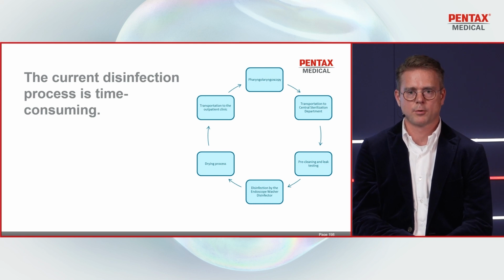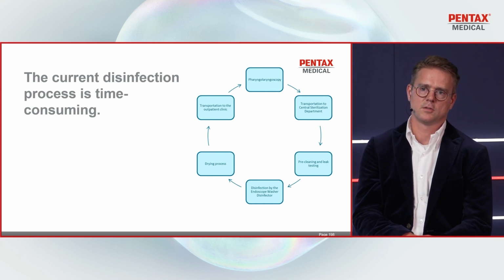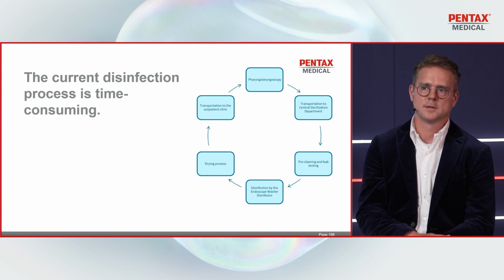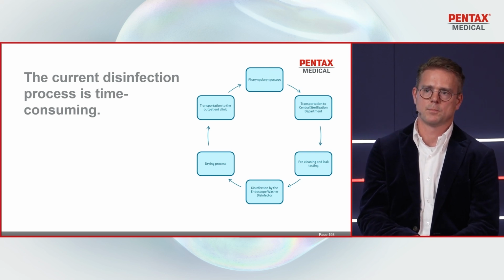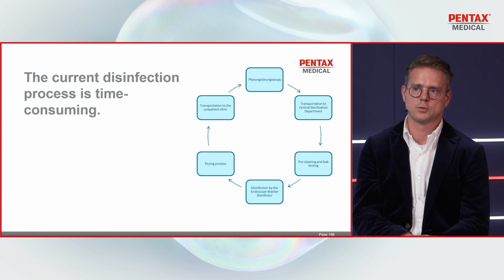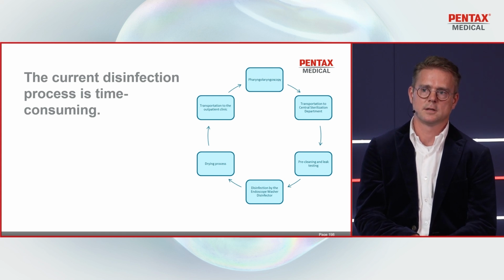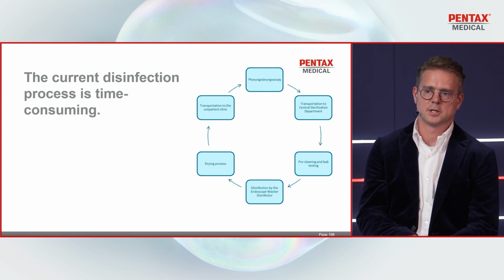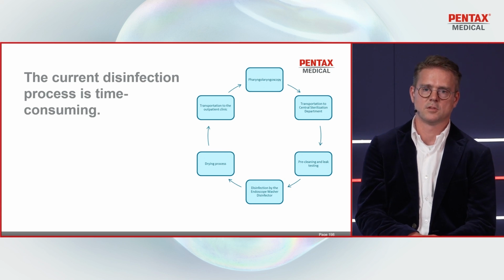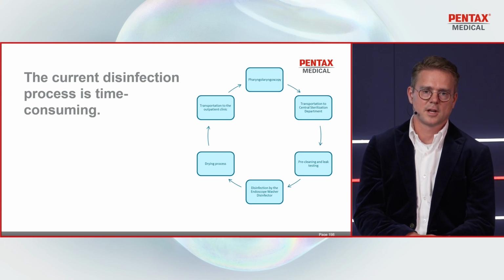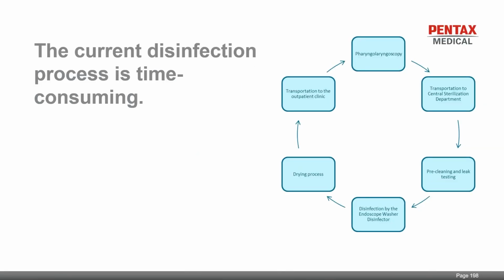There's a big problem right now: the current disinfection process is very time-consuming. After the endoscopy, the endoscope has to be transported to the central sterilization department, where it is pre-cleaned and leak tested. After that, the endoscope goes into the washing machine, and the washer disinfector will disinfect it. After that, a drying process is needed, and then the endoscope goes back to the ENT department again. That can take up to 6.5 hours, so that's very time-consuming.